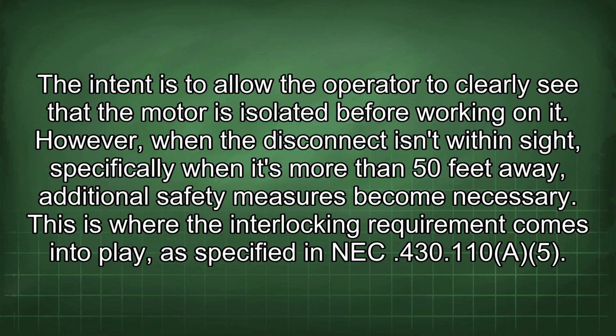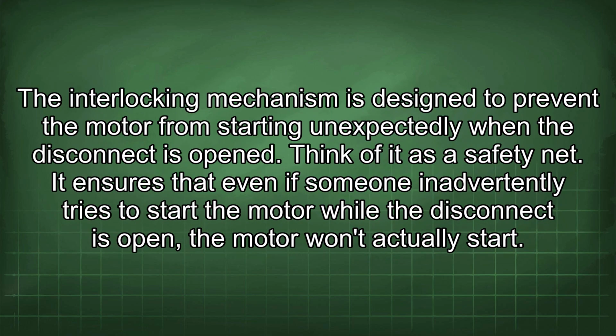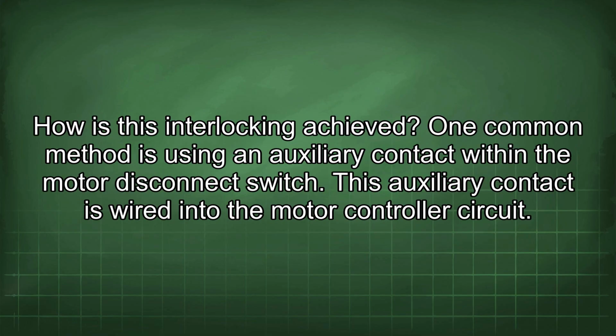This is where the interlocking requirement comes into play, as specified in NEC 430.110. The interlocking mechanism is designed to prevent the motor from starting unexpectedly when the disconnect is opened. Think of it as a safety net. It ensures that even if someone inadvertently tries to start the motor while the disconnect is open, the motor won't actually start. How is this interlocking achieved?